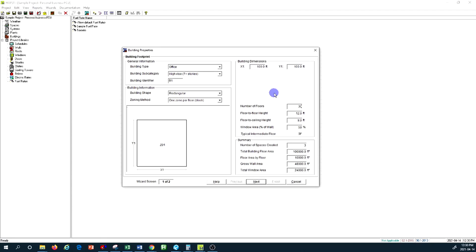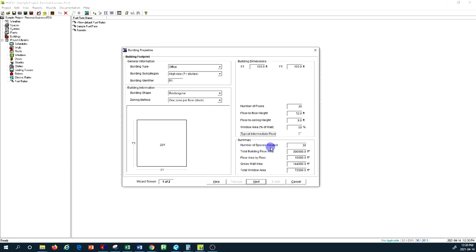Basically the medium level would be the same as all other floors with the exception of ground and top floor. But if you keep it unchecked, then you're given the calculation for every single floor. I'm going to keep this as checkmarked, so you see the number of spaces that Carrier HAP creates is 30, but when I checkmark it it becomes three.